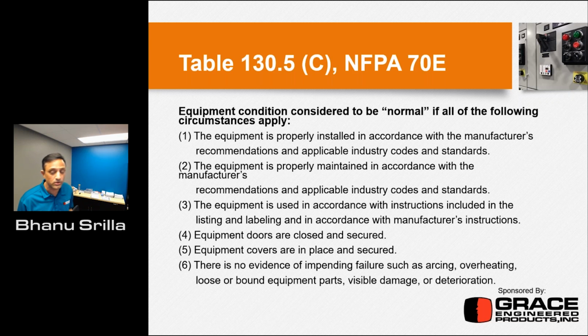So equipment doors are closed and secured. You can't say this system is in normal operation keeping all the doors open, right? I mean, if you want an example, thermography is allowed because it's diagnostic work, and somebody is taking measurements for temperature monitoring by opening the door, and these people are also qualified persons per NFPA 70E. And equipment covers are in place and secured, and there is no evidence of impending failure such as arcing, overheating, loose or bound equipment parts, visible damage or deterioration.